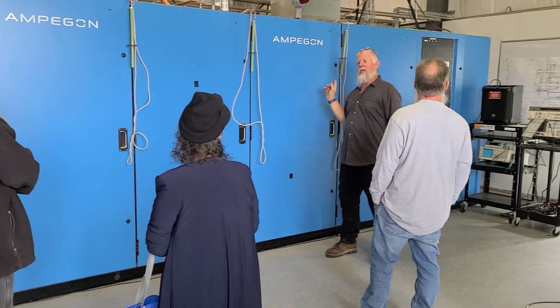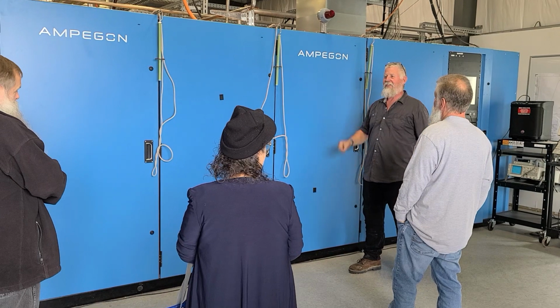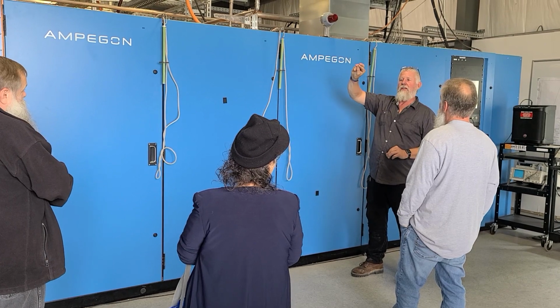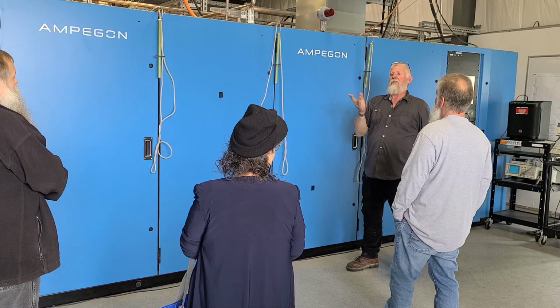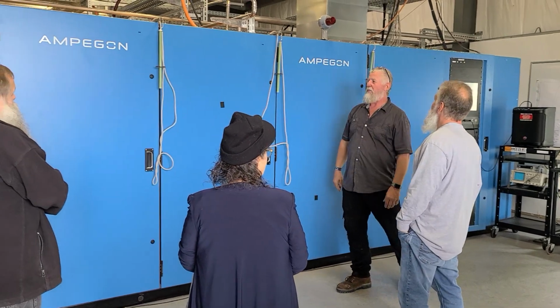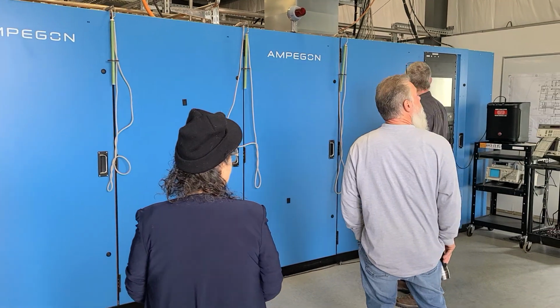It began to sense, and it would spark off inside. You would go bang like that, and it would kick it offline. That's just because those wires on the antenna are 7 strands, and the wind must have broken 6 of them, and then it melted the last one because all 300,000 watts of power were going through this bundle. So then we crawled up there when we discovered it and repaired it by putting 7 strands on the top again.